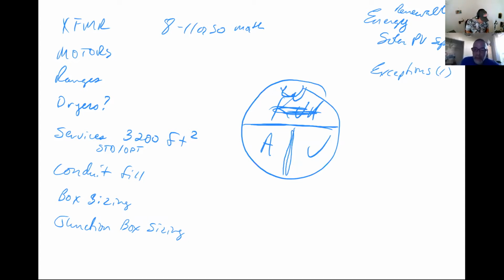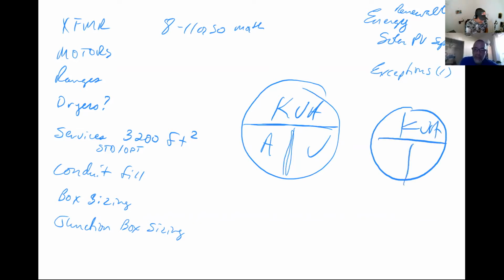That's why to me it's so simple. Once I've made that mental note, okay, I don't have to worry about it. If I have a transformer calculation where I only have the voltage and a kVA rating, and they give me this other piece on the secondary side, I can do this. All I know is that kVA, and look at it like this: it's kVA on the secondary side as well. So technically you've got the same formula on the primary side as you have on the secondary side.